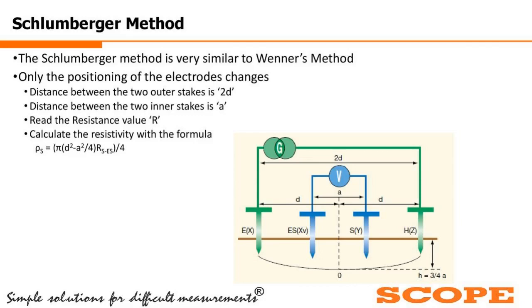Then the formula is a bit difficult, not so easy to remember. Rho S, or the desired resistivity, is pi into D square minus A square by 4 multiplied by R. R is the resistance between these 2 points, S and ES, these 2 blue portions. So the resistance between this zone, whatever has been displayed on the meter, will be multiplied, and finally the entire value has to be divided by 4. So this is the Schlumberger method calculation.